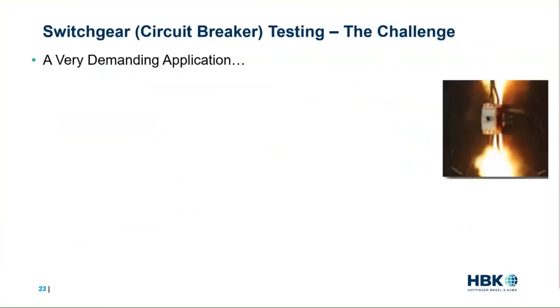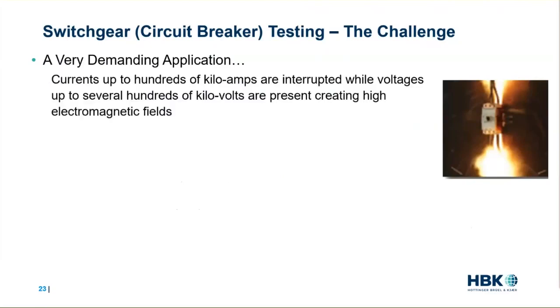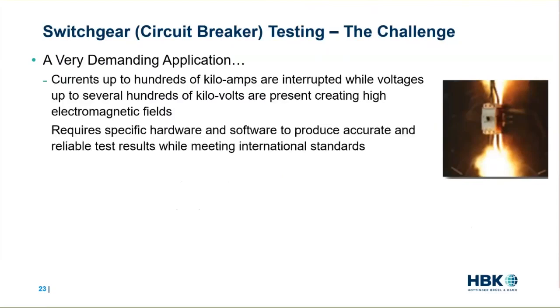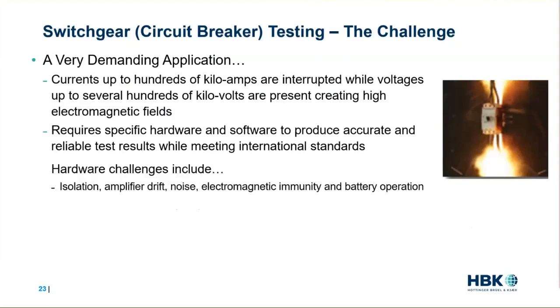Now, our next application is switchgear testing, or circuit breaker or fuse testing. And this is a very demanding application with several challenges. For example, you're dealing with currents up to hundreds of kiloamps, which are interrupted while voltages of up to several hundreds of kilovolts are present, creating high electromagnetic fields. In fact, this requires specific hardware and software to produce accurate and reliable test results while meeting international standards.